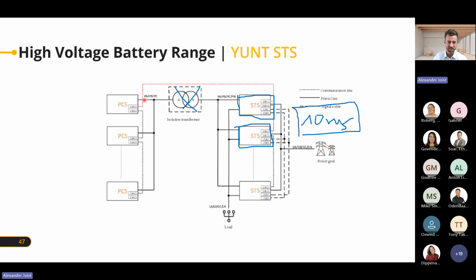Up to 8 PCSs can run in off-grid mode. So then, instead of using STSs, you could also use any changeover switch, right? Which takes a bit longer, same as when you switch over to your generator, exact same thing. You switch over to your PCSs, or you switch off the grid supply, and then you restart the PCSs, 8 of them, to create an off-grid system with 8 PCSs maximum.